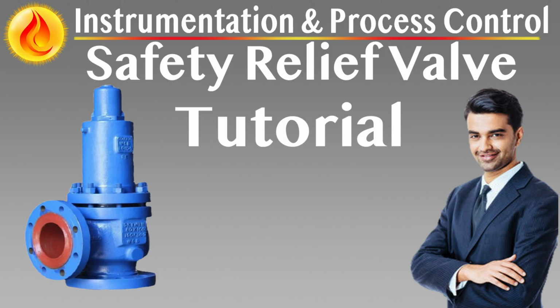Non-balanced spring-loaded relief valves: direct-acting simplicity for low back pressure applications. Non-balanced spring-loaded relief valves are the standard choice for most general service applications, offering a straightforward and reliable mechanism for pressure protection. They operate by using a mechanical spring to oppose system pressure on the valve disc. When system pressure exceeds the calibrated set pressure, the spring compresses, the disc lifts, and fluid is vented. When pressure falls below the reseating threshold, the valve closes automatically.